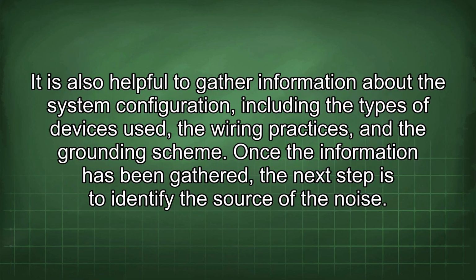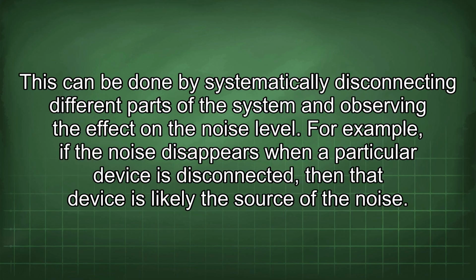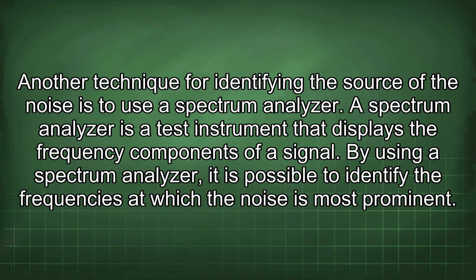It is also helpful to gather information about the system configuration, including the types of devices used, the wiring practices, and the grounding scheme. Once the information has been gathered, the next step is to identify the source of the noise. This can be done by systematically disconnecting different parts of the system and observing the effect on the noise level. For example, if the noise disappears when a particular device is disconnected, then that device is likely the source of the noise. Another technique for identifying the source of the noise is to use a spectrum analyzer.